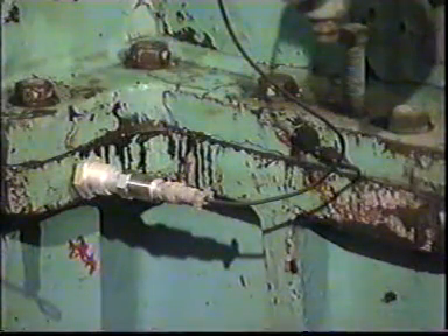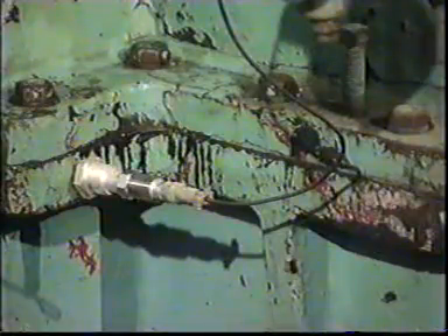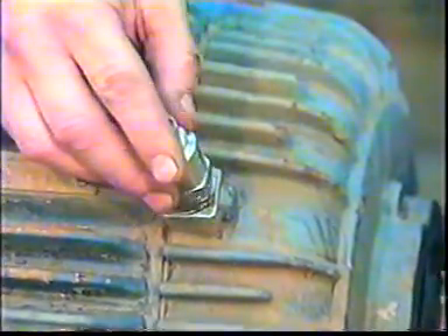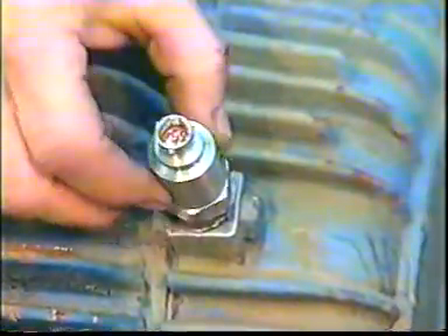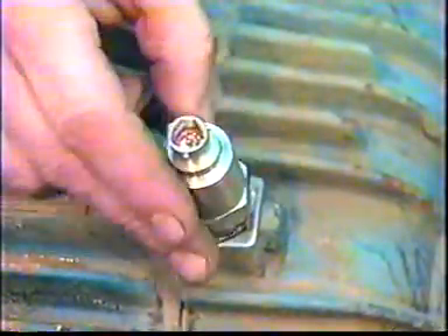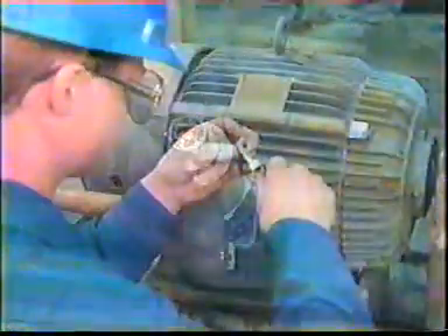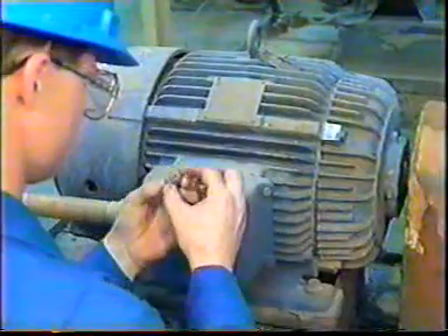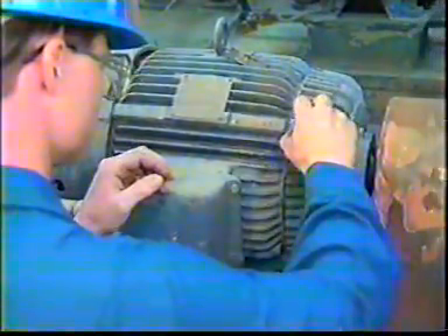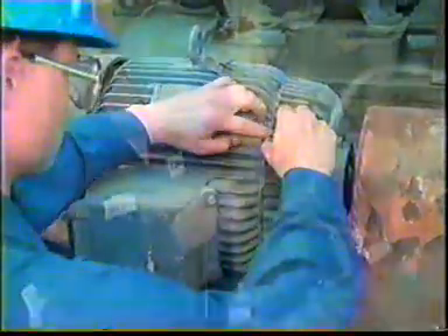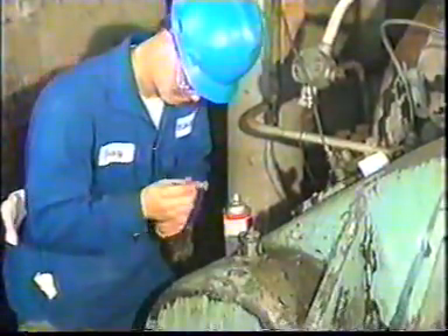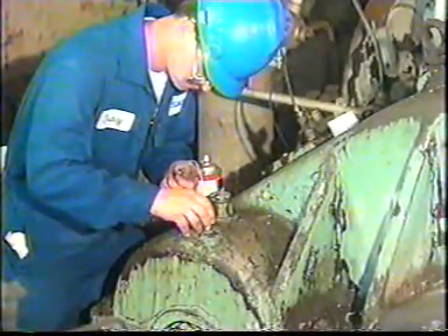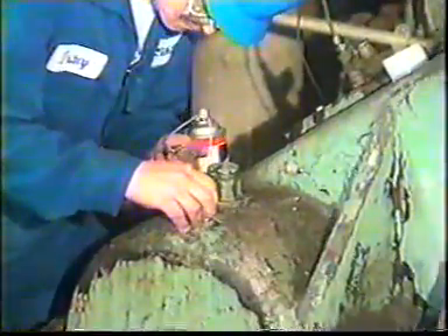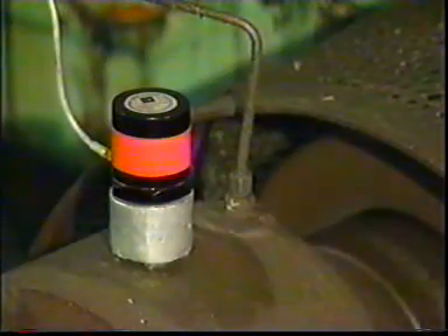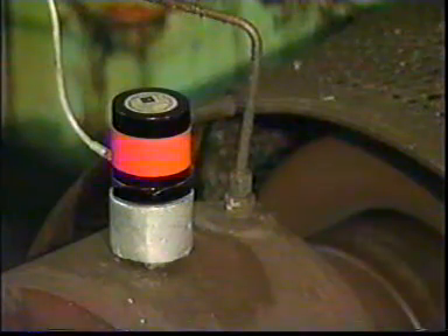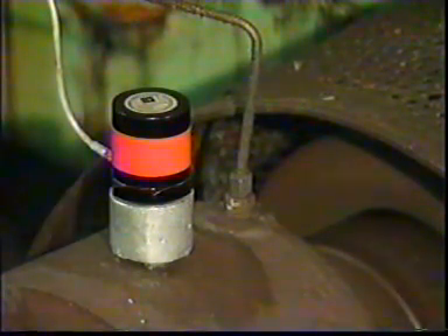A stud-mounted sensor provides the best high-frequency measurements. A stud mounting has a short, stiff stud welded or permanently threaded into the machine's surface. This method provides a relatively flat response to high frequencies. Cementing or permanently bonding the sensor to the machine's surface also provides flat response out to higher frequencies. Sensors can be temporarily mounted with sealing wax to keep contact with the machine. This method provides a flat response for medium frequencies. A magnet is a common temporary mounting method. It will also provide a flat response for medium frequency ranges.